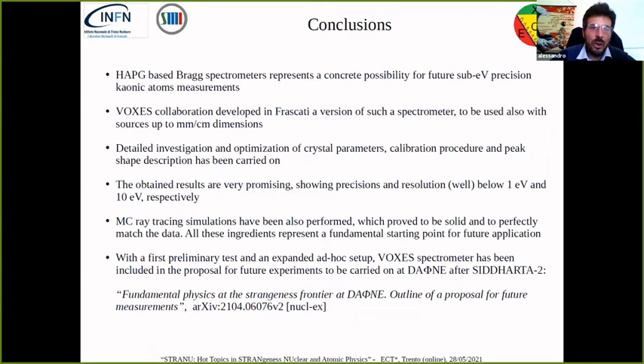We have already performed a detailed investigation and optimization of all the crystal parameters, the calibration procedure, and the peak shape description. This is very important because you have to keep all these parameters under control when you perform future measurements. The obtained results are very promising because we already obtained precision and resolution below one electron volt and 10 electron volt respectively. And we proved to have a solid set of Monte Carlo ray tracing simulations perfectly matching the data. All these ingredients really represent a fundamental starting point for our future applications.